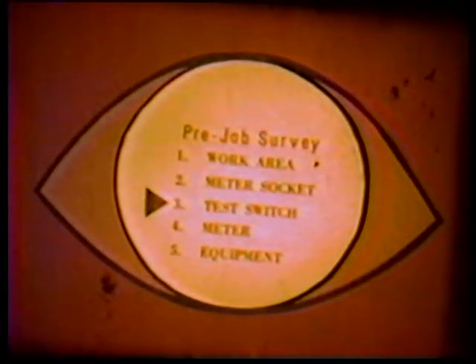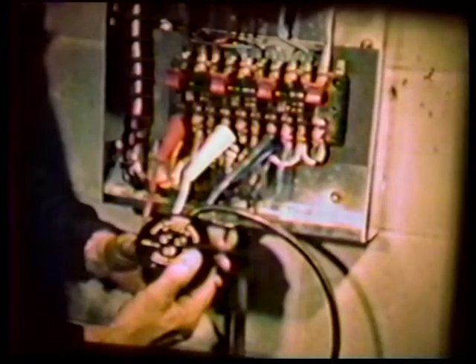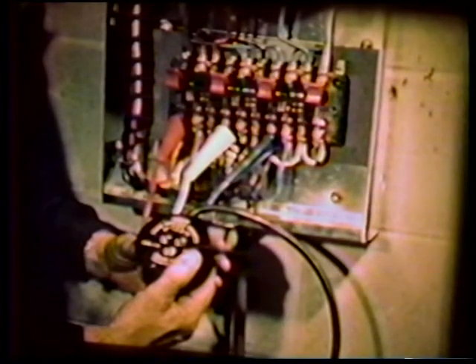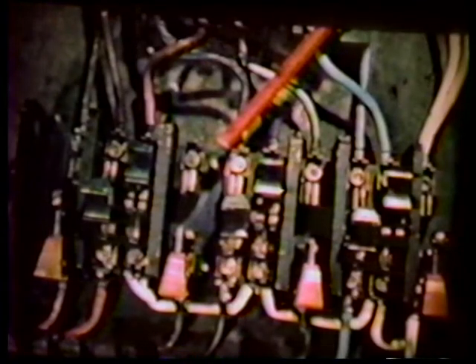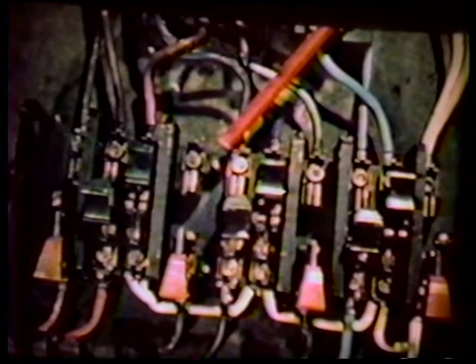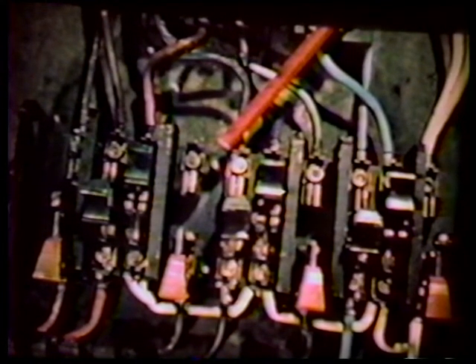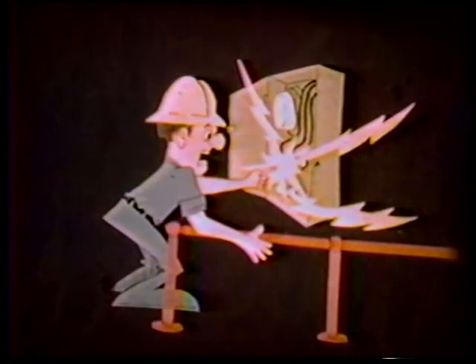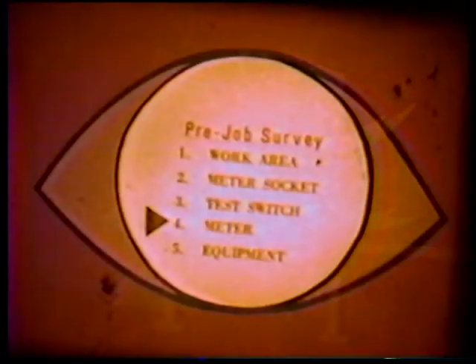Now let's talk about meter jobs that require test switches. Check the general condition of the test switch. Check switch phase sequence and secondary wiring. If barriers between line parts and ground are low or completely absent, special caution is required. Check for proper wiring to be sure you do not close in on a ground.